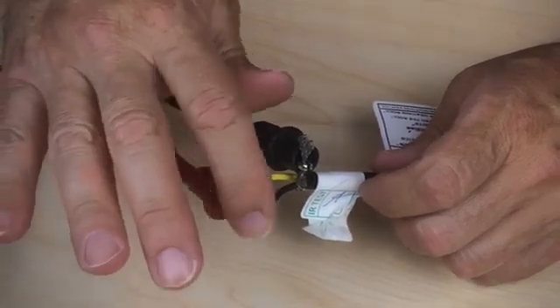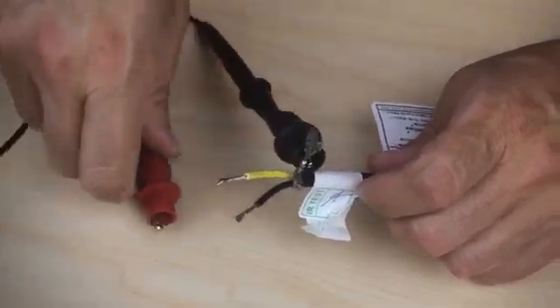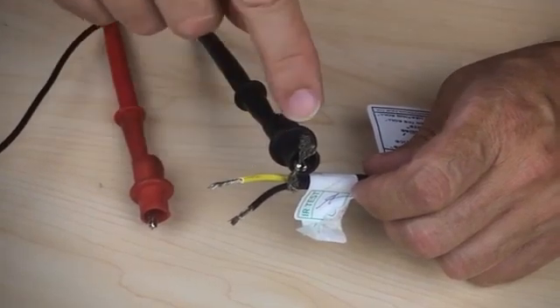To recap, you don't want any reading from the black wire to ground or from the yellow or red wire to ground. And that's how you troubleshoot a GFI issue with the Warmly Yours system.